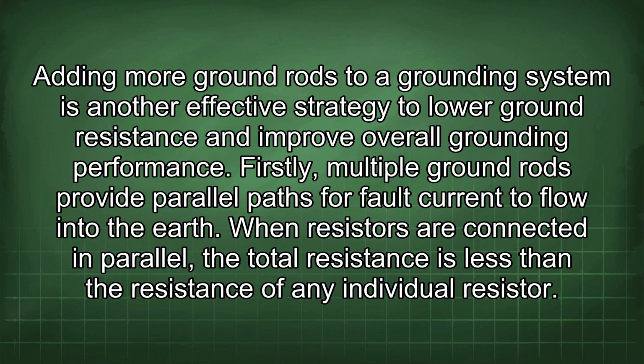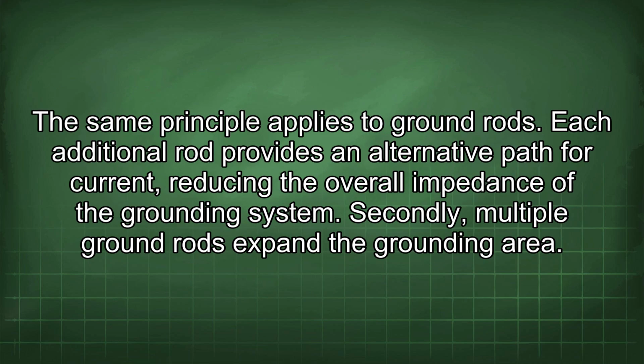Adding more ground rods to a grounding system is another effective strategy to lower ground resistance and improve overall grounding performance. Firstly, multiple ground rods provide parallel paths for fault current to flow into the earth. When resistors are connected in parallel, the total resistance is less than the resistance of any individual resistor. The same principle applies to ground rods. Each additional rod provides an alternative path for current, reducing the overall impedance of the grounding system.